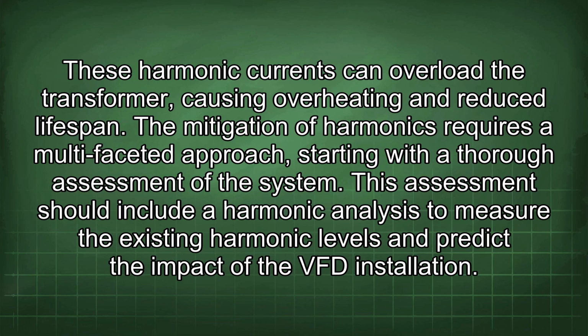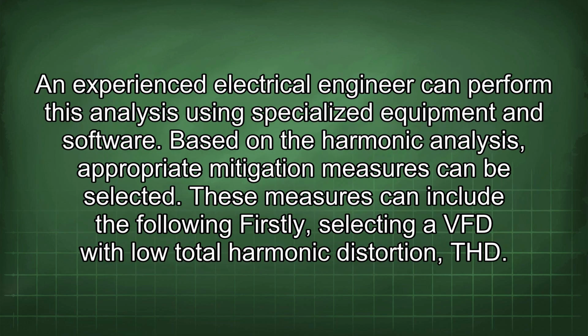This assessment should include a harmonic analysis to measure the existing harmonic levels and predict the impact of the VFD installation. An experienced electrical engineer can perform this analysis using specialized equipment and software. Based on the harmonic analysis, appropriate mitigation measures can be selected. These measures can include the following.